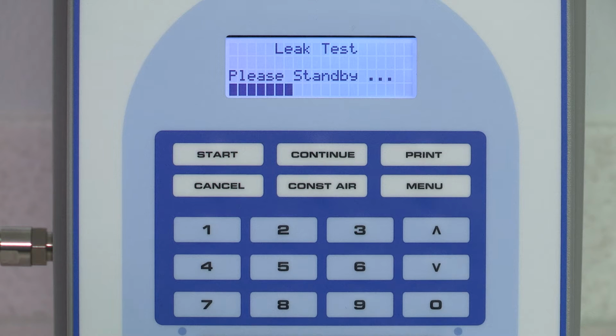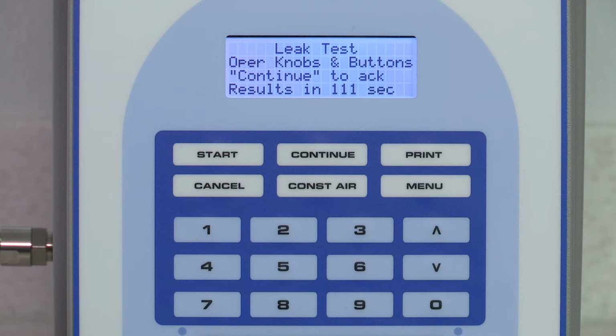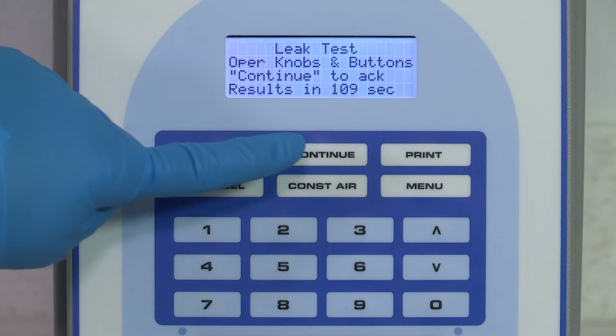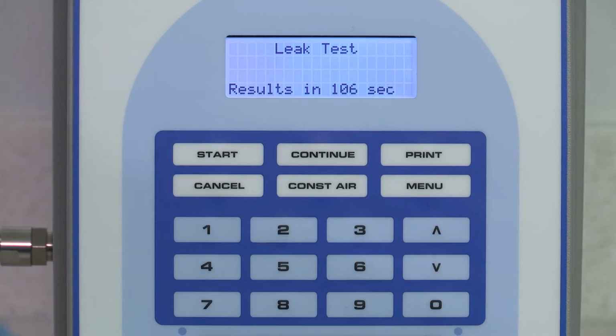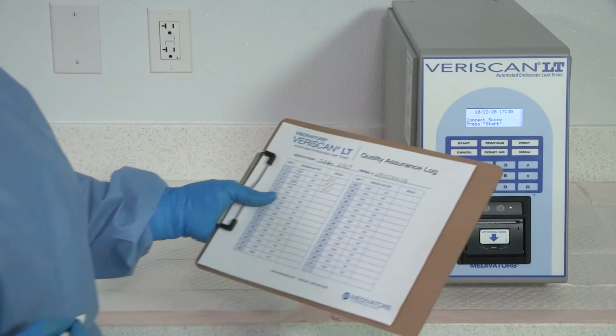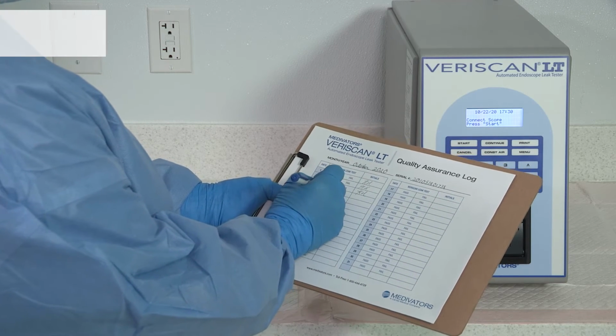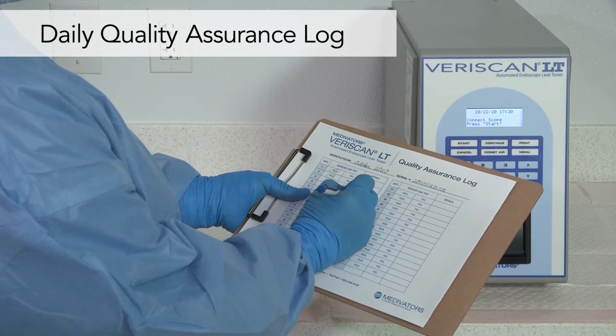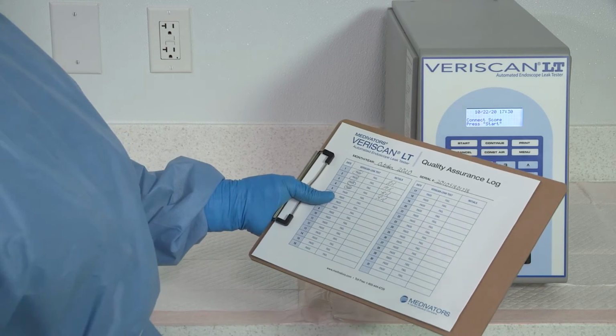The screen displays Leak Test. Please stand by. You will hear the air pump cycling on and off during the leak test. After a preset period of time, an audible tone sounds, and the screen displays Leak Test. Operate knobs and buttons. Press Continue to acknowledge. Press the Continue button and the leak test will automatically resume. After completion of the test, an audible tone sounds, and the screen displays Pass or Fail. Record the daily QA pass or fail test result using the daily quality assurance log provided in the in-service packet or found on our website under the product page.